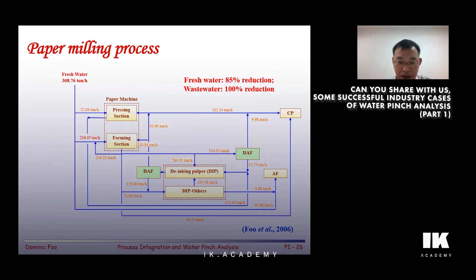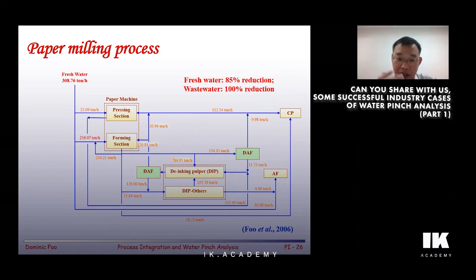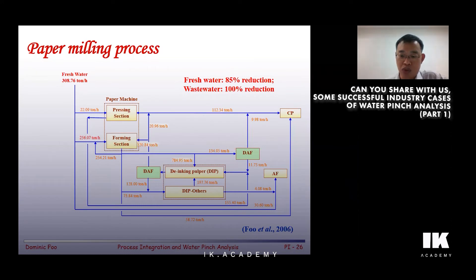So when we did a water pinch analysis, it actually can help to reduce fresh water to 85% and wastewater to 100%. However, this is using what we call the grassroots design method. It means that we have to redesign the whole plant, which is not too practical because it's already a plant that is in practice and running in operation. If you have to redesign the whole thing, the plant has to shut down for a few months, so not too realistic.